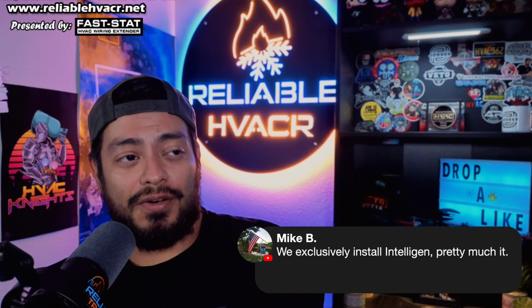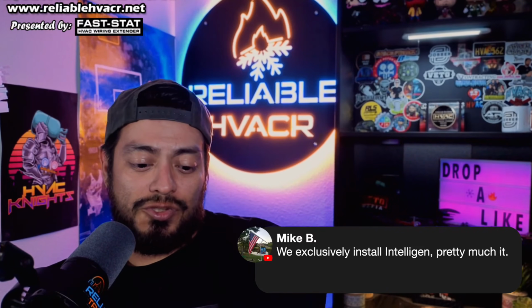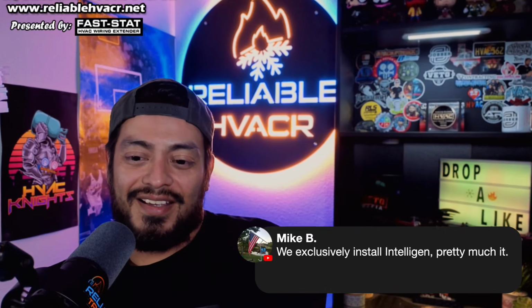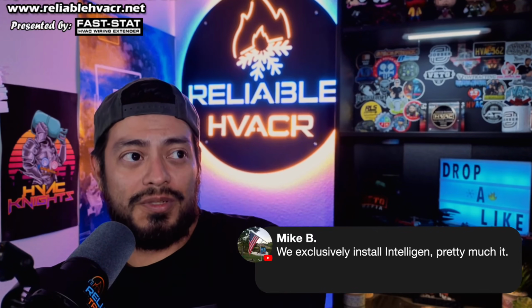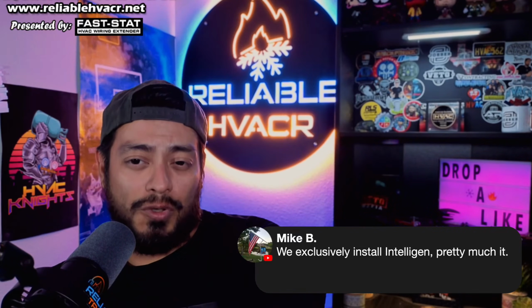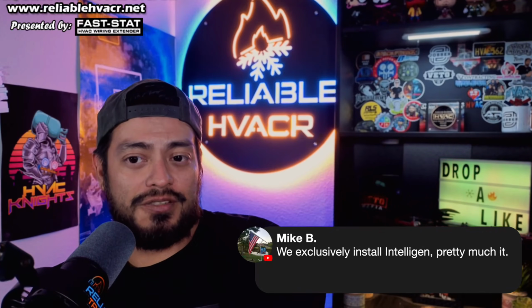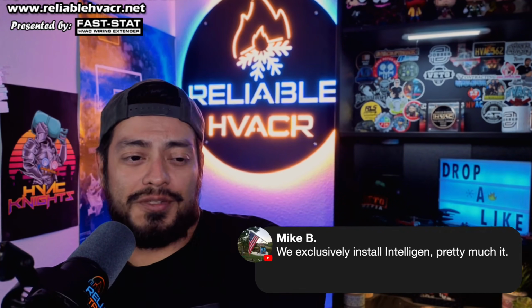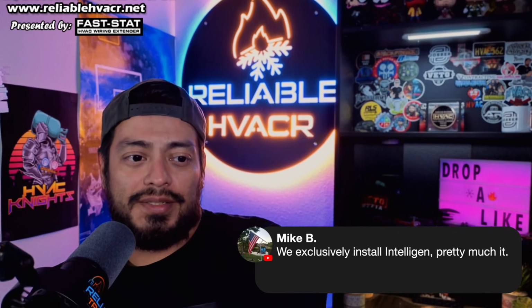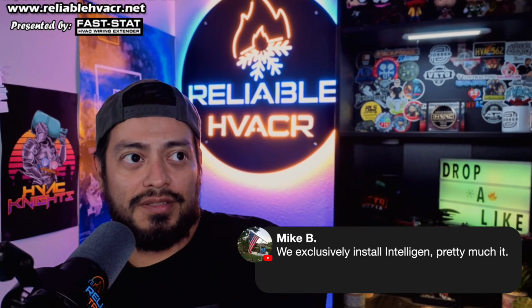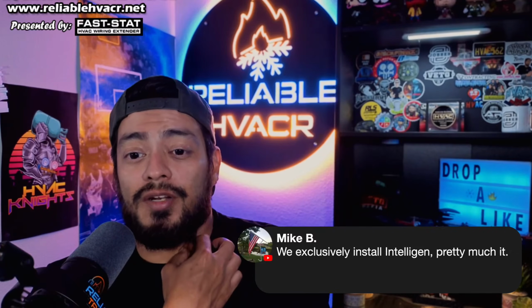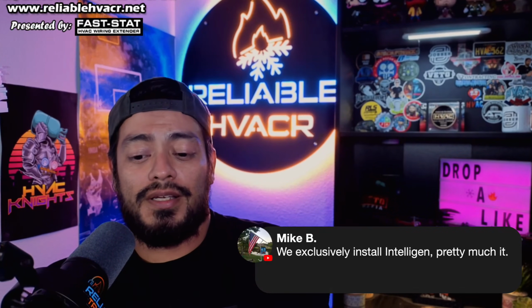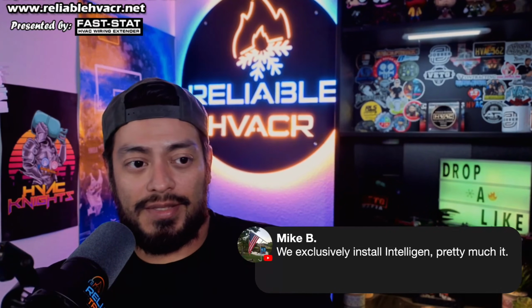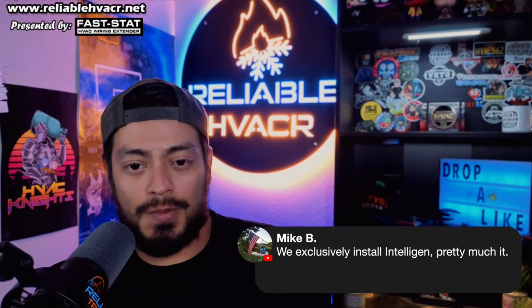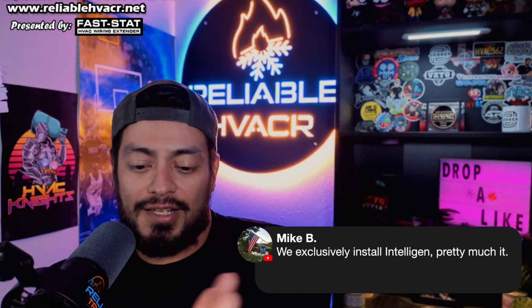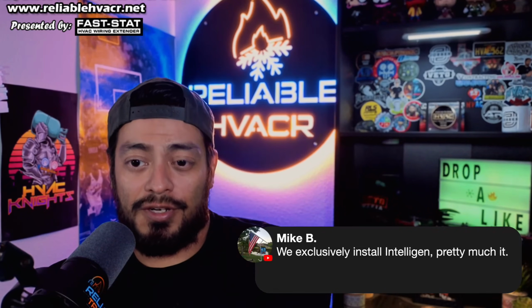Whereas with Russell, I needed to call them again because the guy had me change out two motors and the board. The motors were working when I changed them out, because I had issues with them turning off. But the new one stayed on, though it still wants to stay in low speed. Everything I know says it should be calling for high speed - we've already met the temperature, pressures are good, superheat's good, we're getting into the 20s. It has a set default of 35 degrees for it to switch.